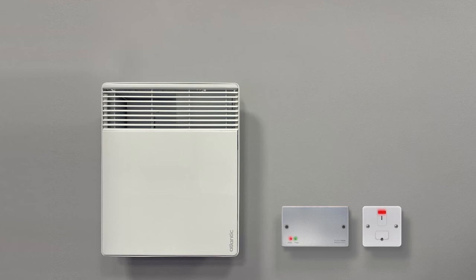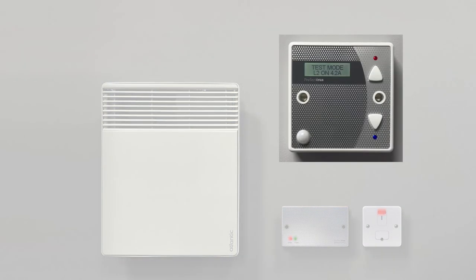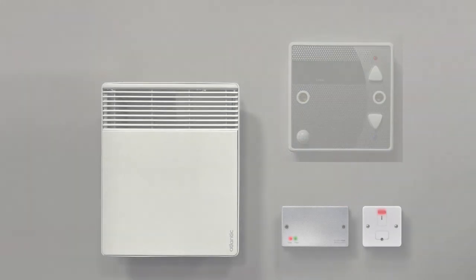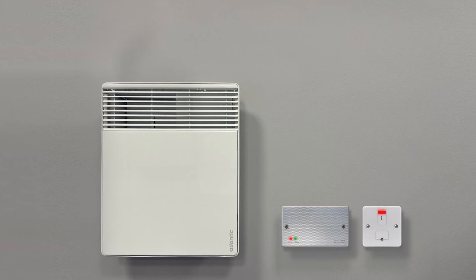New panel heaters will give off vapor and an odor when switched on for the first time. It is good practice to open the window while carrying out this test. We recommend a burn-off period of at least 2 minutes to ensure that when the occupant returns and uses the heater for the first time, the fire alarm is not activated. After 2 minutes in test mode, the control unit will revert to standard operation. If the heater is still giving off vapor, please repeat this process.